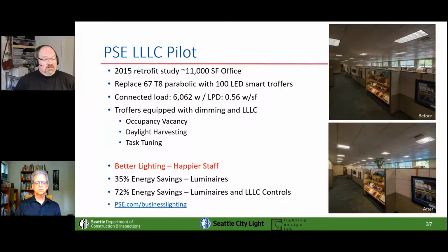This was 6 years ago. What is our current open office lighting allowance now, Mr. Duane? I forget. 0.55. So 6 years ago, it was 0.01 higher. Now the fixtures are equipped with occupancy, vacancy, daylight harvesting, task tuning.